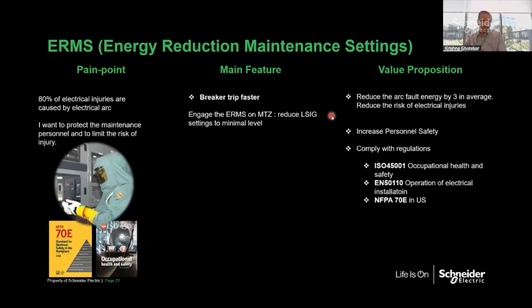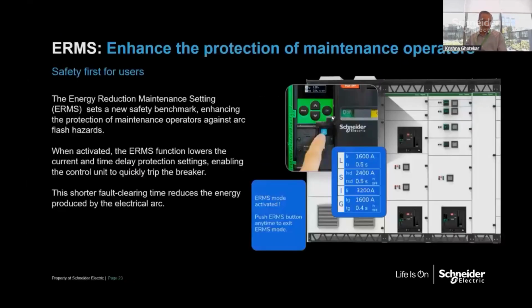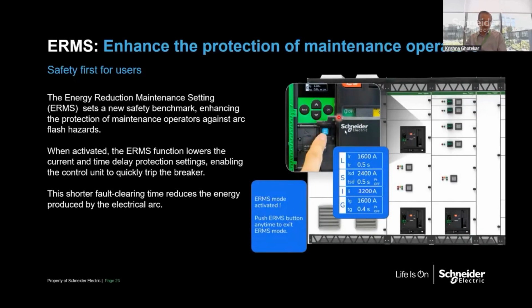So ERMS, which I had mentioned, is a new feature which we are bringing to the market, considering the safety of the operator. Again, the facility guys or the maintenance or the electricians who are working there. So what it means is, in case the operator is there in the electrical room, he just goes, opens the flap on the trip unit, presses the ERMS button, the display will turn blue in color. That means its ERMS mode is activated.